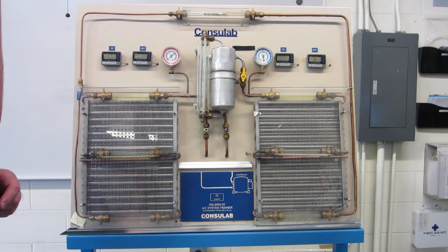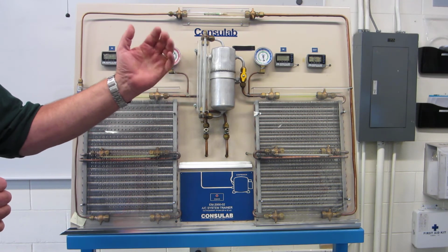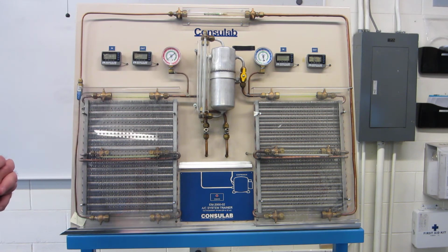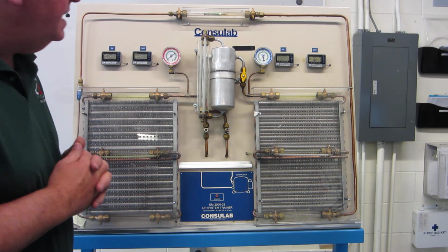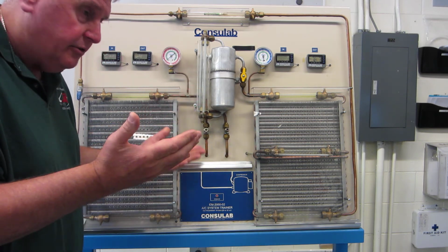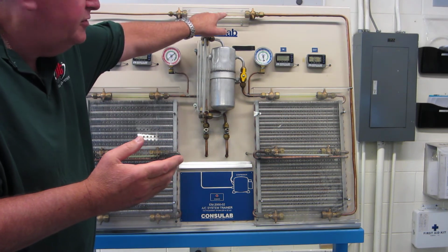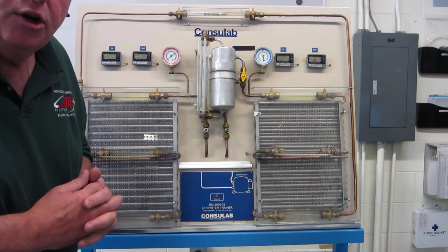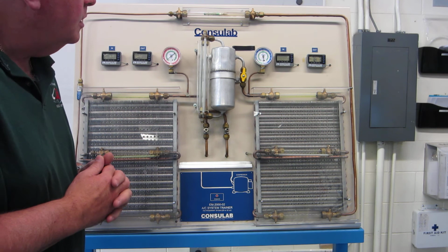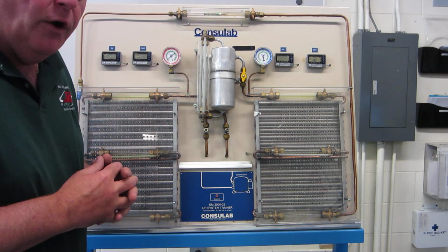Now, this is also maybe a good time to talk about a really cool thing that happens in air conditioning systems. One of the best troubleshooting tools we have is your hand. And we know we've always taught you never use your hand as a troubleshooting tool. But the cool thing that happens in air conditioning is the fact that anytime I have a restriction, you've already learned this, if I have an orifice, I get a pressure drop. I have a pressure drop in the air conditioning system, I get a cold spot or a cool spot. And on a really cool day, you might see frost forming.